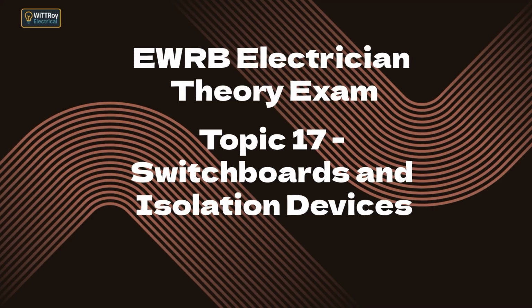A distribution switchboard, sometimes called a subboard, is supplied from the main board and distributes power to circuits in a specific part of the installation. It must have correctly rated protective devices, proper segregation, clear labeling, and safe access. Even though fault current is lower than at the main board, the board must still meet the required short-circuit ratings, enclosure requirements, and wiring space. Across all boards, AS/NZS 3000 requires safe access, correct IP ratings, mechanical strength, suitable ventilation, and proper marking so that electricians can operate and maintain them safely.